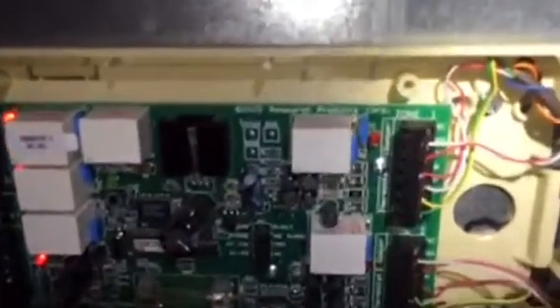This one here is showing closed. This one here — I'm not 100% sure, but this damper is in position. You can see the little arm inside there. I'm going to double check and see if there's 24 volts going to both of these — which one is getting 24 volts and which one is not. One thing I am noticing on the control board is that for zone one and zone two, the red LED lights on this side should show which zone is on, and both of them are clearly off.